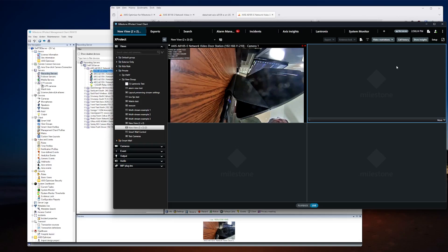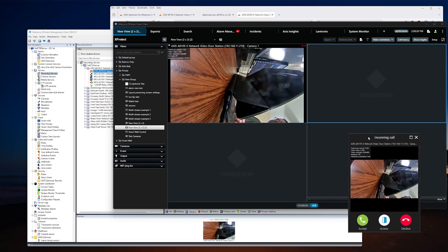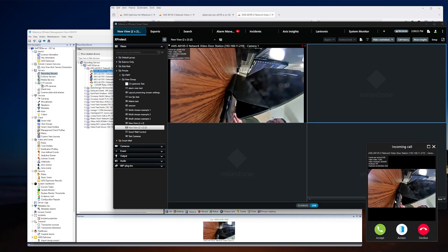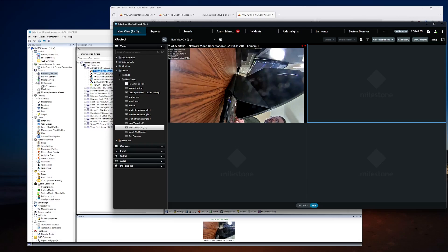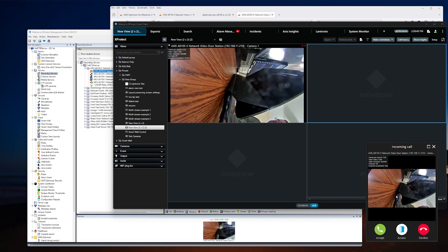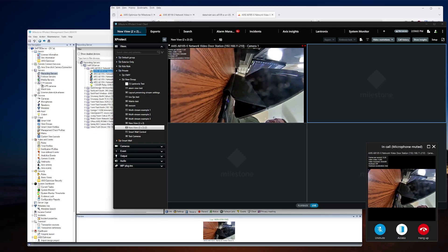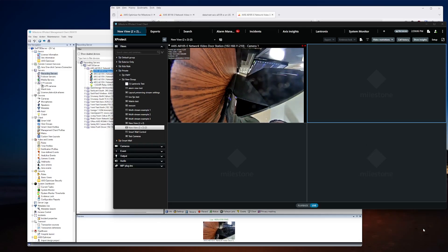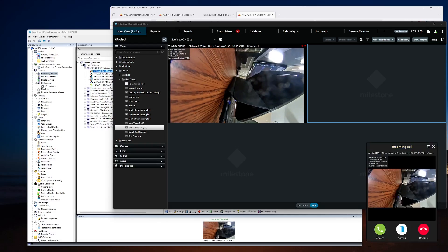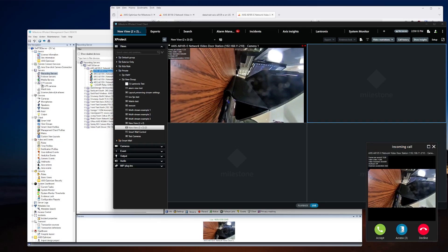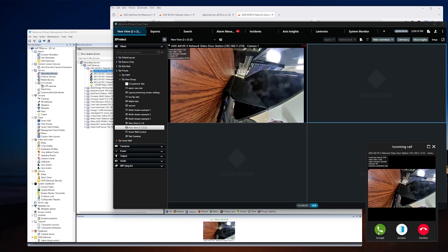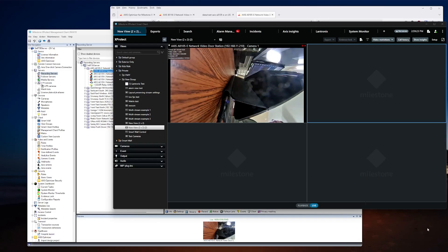Once set up, you can test it — I'll hit the button on the front of the intercom. It pops up on your primary monitor with a feed from the intercom coming in, and you can choose to answer it or decline the call. I'll unmute the desktop audio so you can hear what it sounds like coming through Milestone. There was some feedback because the device was on my desk, but you get the idea. That gives you the ability to speak through it, and if you want to open the door, you can hit the access button, which activates the output to buzz open the door.